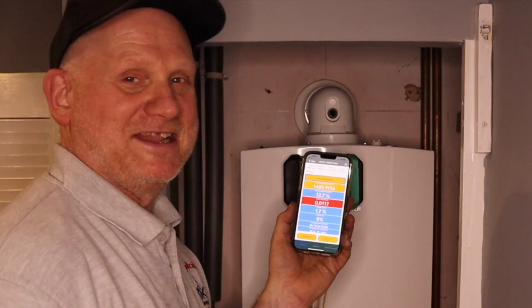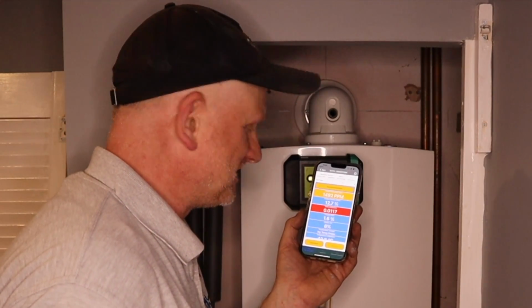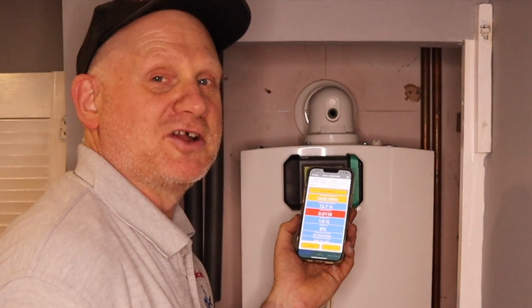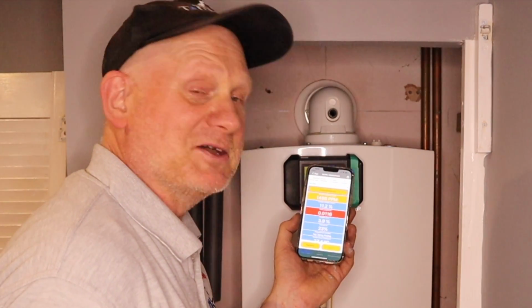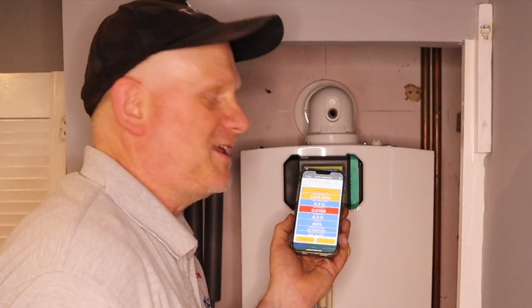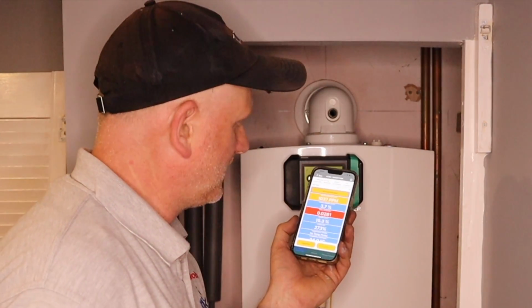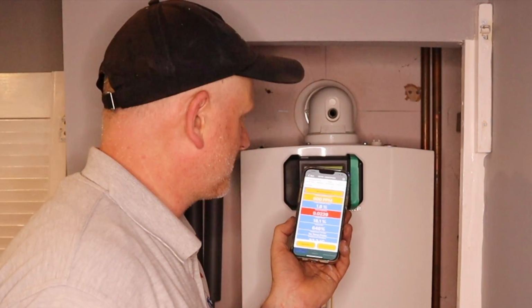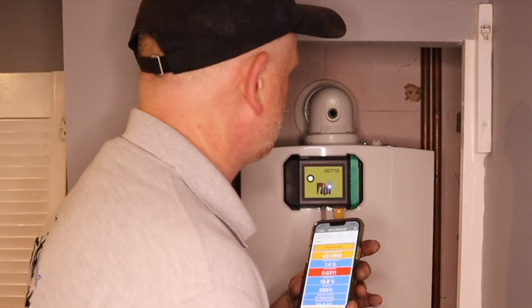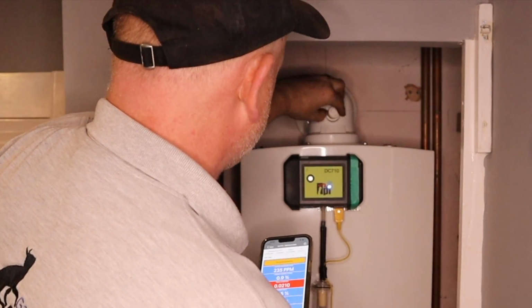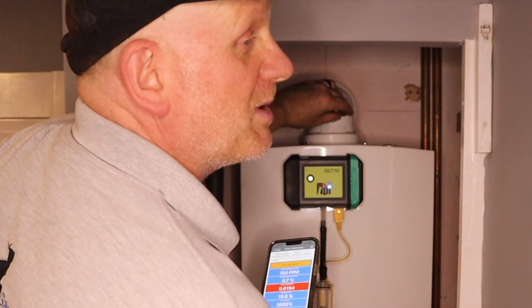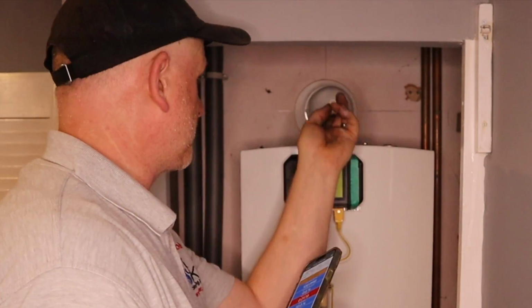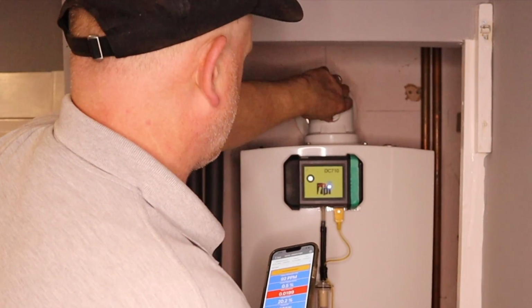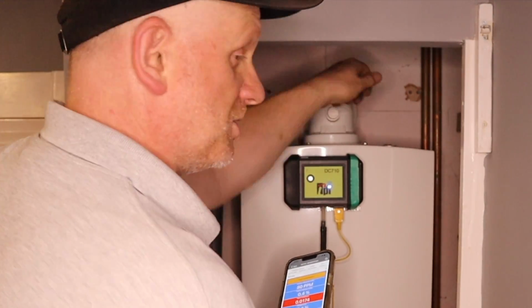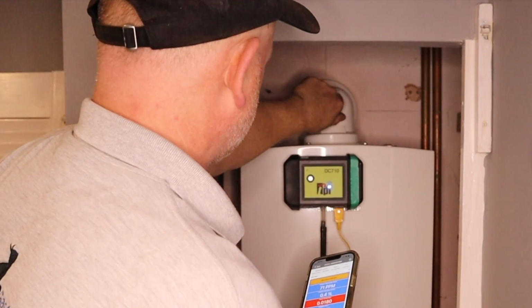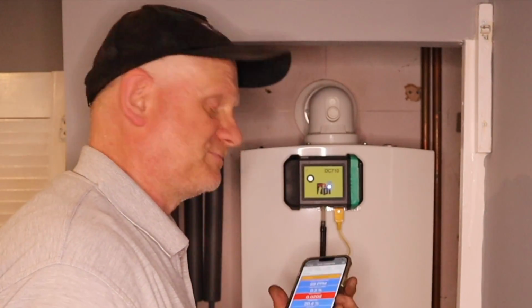Don't really want to be knackering the analyzer, so yeah, I've now got an at-risk boiler. So what a waste of a day this has been, but at least it's shown how bad my boiler is, and we've actually bought a house with a boiler which has never been serviced by the looks of it and needs ripping out. It's the first time ever I've taken a test nipple off on a boiler and it's actually been full of aluminium oxide. So it's going off and a new one going in.